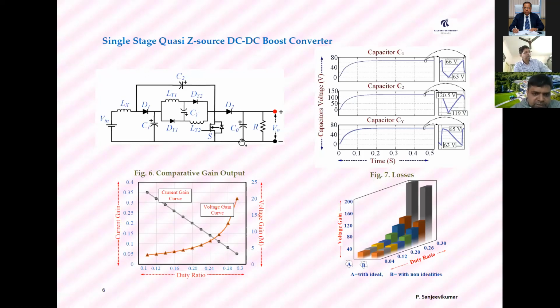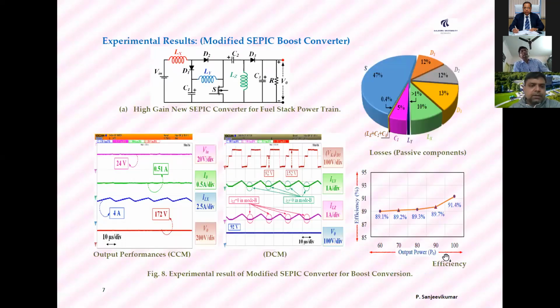Once the converter is designed, we look at the theoretical aspects of how it benefits compared to other solutions. If we utilize this DC power from renewables between 10% to 30%, at around 30% utilization we get 22 times the gain, which is much better than existing solutions allow. With a slight adjustment of passive components, we achieve 22 times gain at only 30% utilization. The most important aspect is loss analysis: under ideal conditions, we can reach a maximum gain of around 200, but when losses are considered—switching losses, conduction losses, passive losses, and EMI losses from active components like MOSFETs and IGBTs—the gain comes to around 194. This is acceptable at 30% utilization.